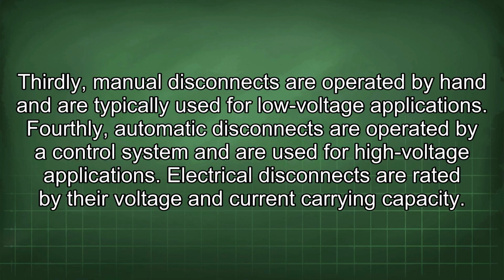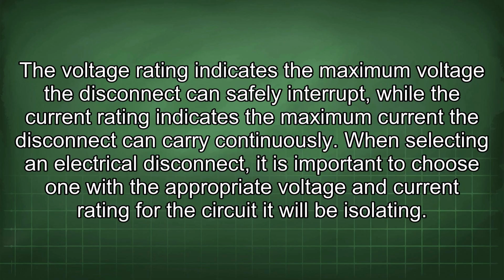Electrical disconnects are rated by their voltage and current carrying capacity. The voltage rating indicates the maximum voltage the disconnect can safely interrupt, while the current rating indicates the maximum current the disconnect can carry continuously. When selecting an electrical disconnect, it is important to choose one with the appropriate voltage and current rating for the circuit it will be isolating.